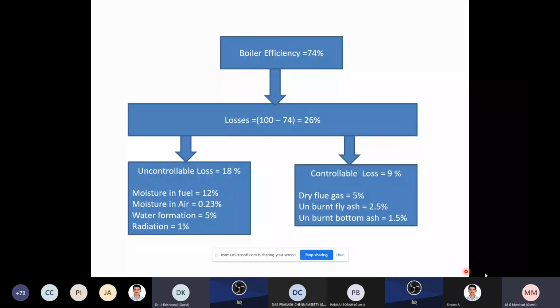Yes. Very important thing for the calculation of efficiency of the boiler. All these things relate to a large-scale thermal power plant, and the boiler is a pulverized mill boiler. It is not a CFBC boiler or other conventional boiler, because the things will change depending on the type of the boiler, but the guideline will be more or less the same. The ideas of energy auditing will be more or less the same. The same data will be there. Rather, calculation-wise it will be somewhat easier. So in this way, the energy auditing team can segregate the data and recommend what actions they can take by seeing all this data.